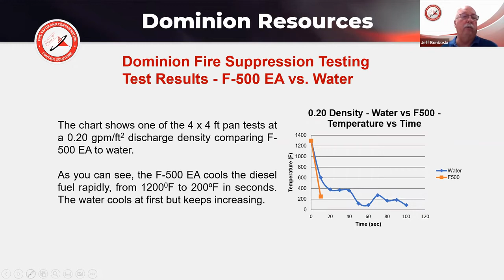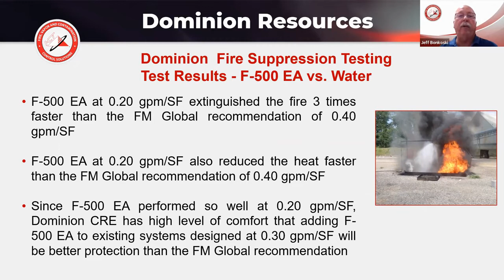And again, this is just a chart showing the temperature and time. When you started looking at the F500, you went from that 1300 degrees down to 200 degrees in 10 seconds, versus with water, it was somewhat fast, got down to 400 and it kind of curved. And it took a while to get to a point where it was able to cool and extinguish. So the test results come back that it's 3 times faster than what is being recommended.